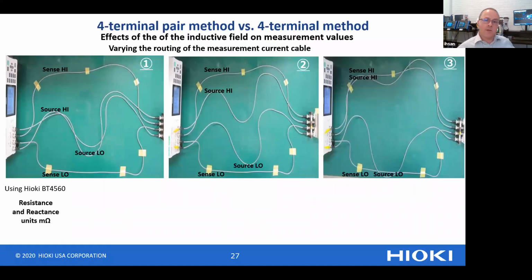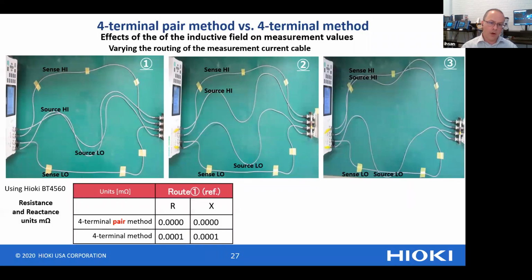Here we have an experiment set up to demonstrate the effectiveness of the 4-terminal pair method versus the 4-terminal method. Picture number 1 on the left shows the Hioki BT4560 battery tester, connected to a 0-ohm dummy load. As you can see, the sense lines, or the connections to the voltmeter, are placed far apart from the current carrying conductors. In this setup, we compare the 4-terminal pair against the 4-terminal method, and the meter is zeroed out. Once the meter is zeroed out, you can see the differences between the two methods are essentially non-existent.